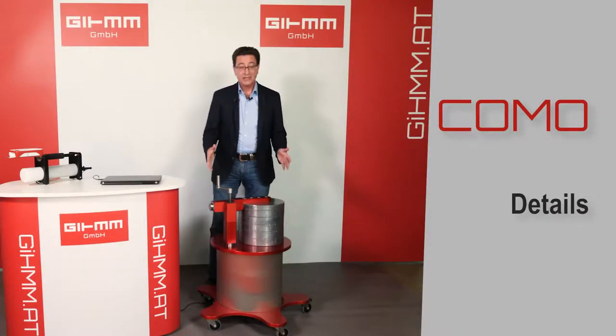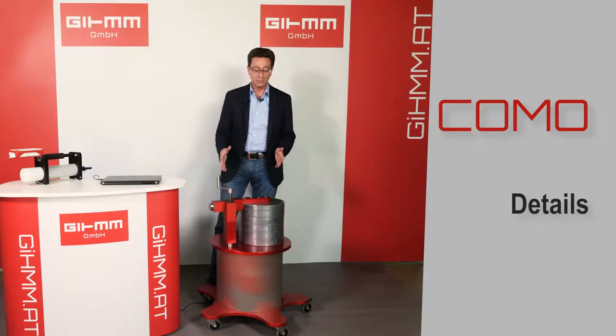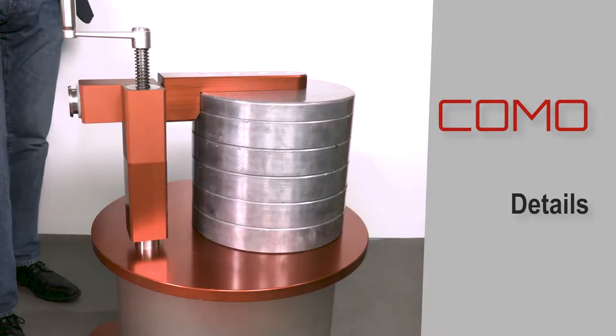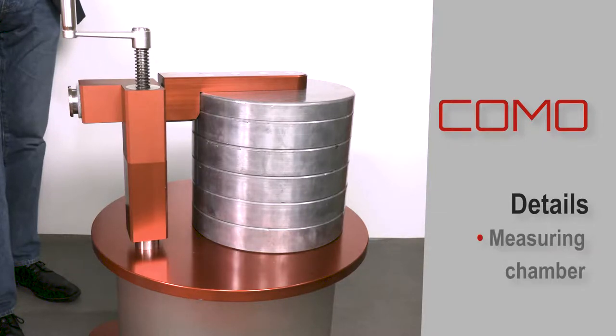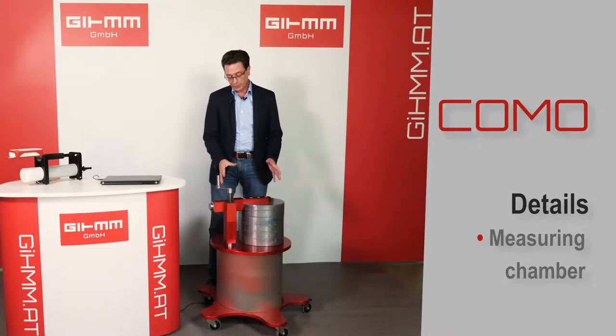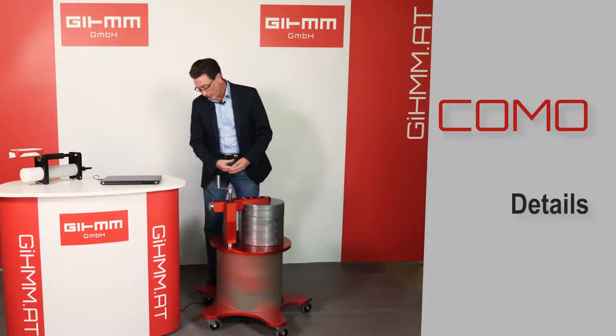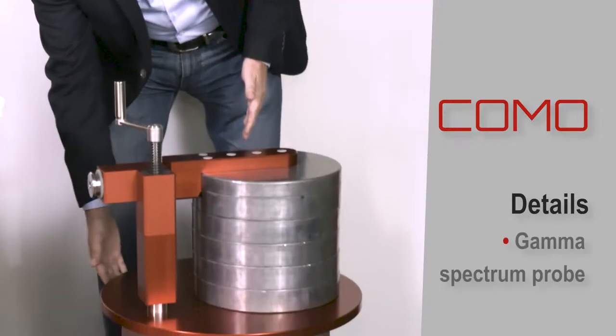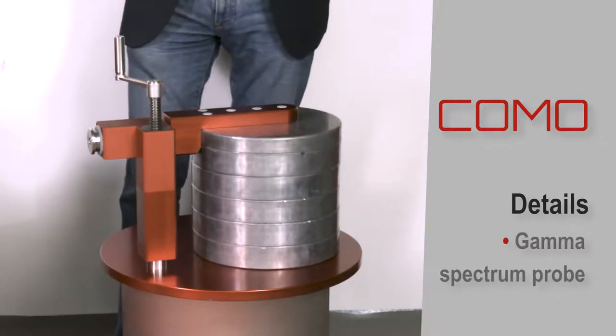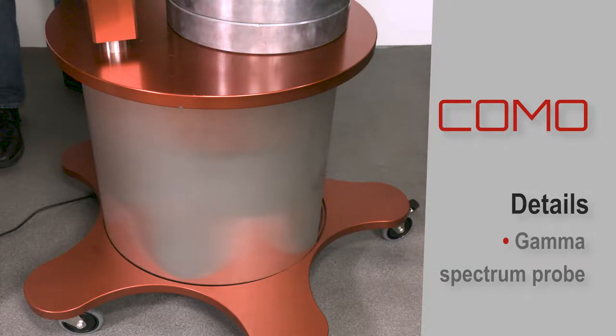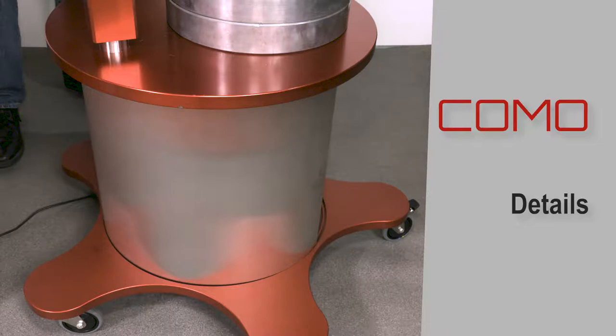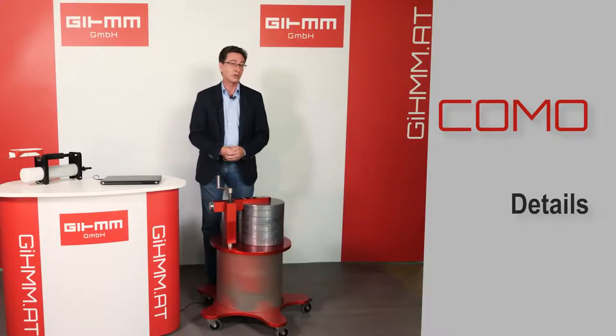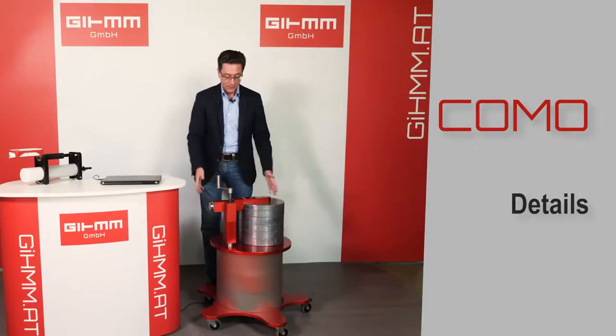Okay, let's have a closer look at the COMO mechanic parts. The first thing which jumps right into our eyes is the massive 35 mm thick lead shielded measuring chamber. This measuring chamber sits on a robust plate and also contains our gamma spectrum probe inside, and underneath it has wheels for being able to place our measuring system at any place where we want to measure our samples.